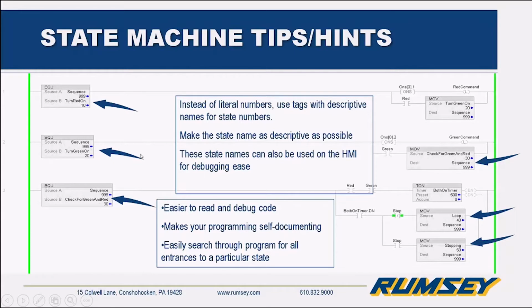Also use the state, because we can now pump up metadata. When I say pump, I mean transfer: the HMI can grab the tag names and put them up on the HMI. So if my sequence is now sitting at, in this case since I have a timer here, check for green and red, or something like that, we can see that sequence through on the HMI. That's another useful idea for using descriptive tags for your states.